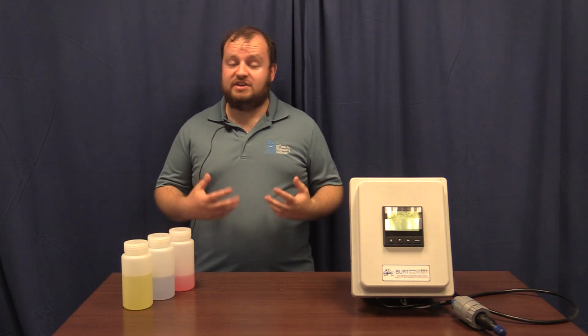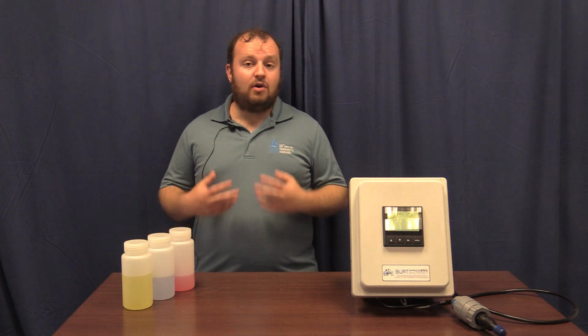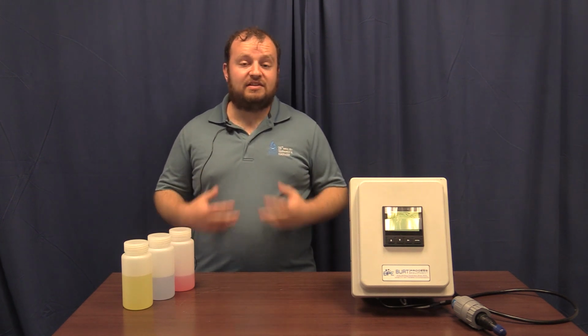So they don't really have an expiration date, but they do have an install date, and probes that are in storage for long periods of time require to be wetted with a saline solution. Over extended periods of time, this solution will evaporate, so you want to make sure you properly check the probe, and if need be, replenish with the saline solution.